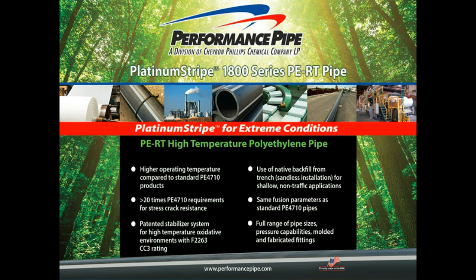Can PERT materials be joined with standard HDPE pipe? That's a great question, and the answer is yes. The same fusion parameters that are used to fuse current PE4710 materials would be used to fuse the PERT material, and you wouldn't have to alter the fusion process when you're mixing and matching current PE4710s with the PERT materials.